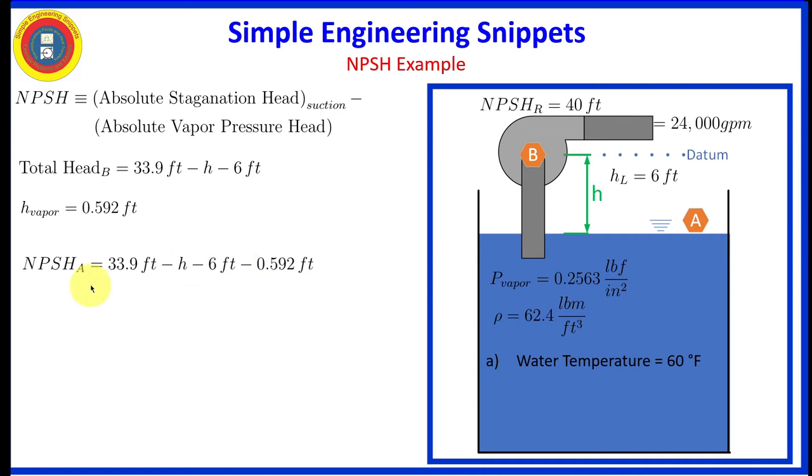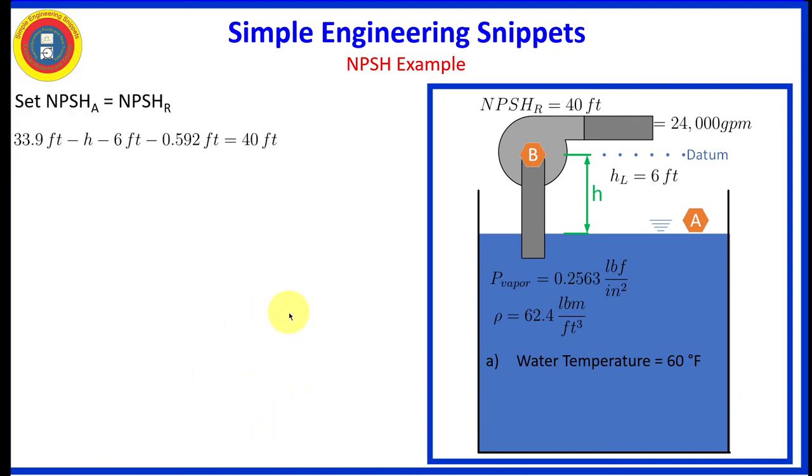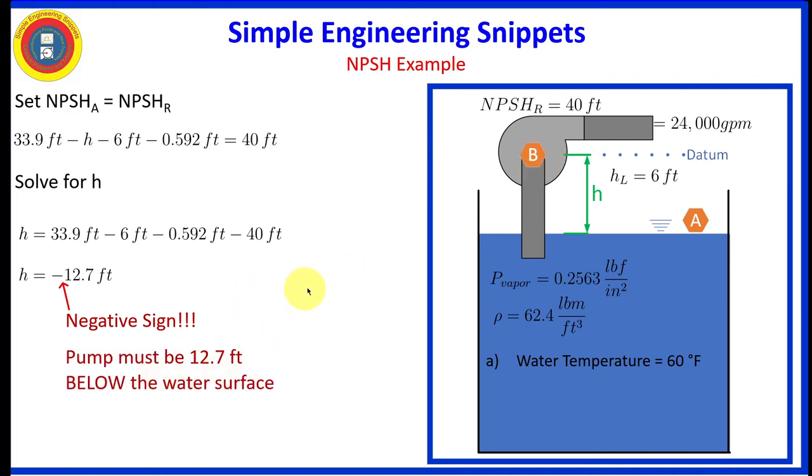Okay, now let's write down our equation for net positive suction head available. And I want to note that this A in net positive suction head is available. This is the actual net positive suction head at the pump suction. It is not, repeat not, location Alpha. This designates the available net positive suction that actually is available with how we have this pump oriented and set up. And again, our supplied required net positive suction head is 40 feet. And to solve this problem, we are going to set the available equal to the required. It contains one equation with our unknown H. And we're going to solve that for H. And when we do that, we get minus 12.7 feet. So yeah, note the negative sign. That negative sign means that our pump, we assumed it would be okay to be oriented above the surface of the water level. That is not the case. It needs to be below the water surface.